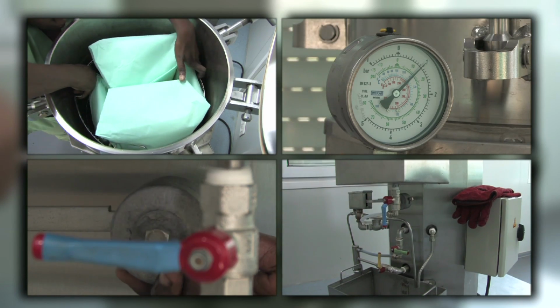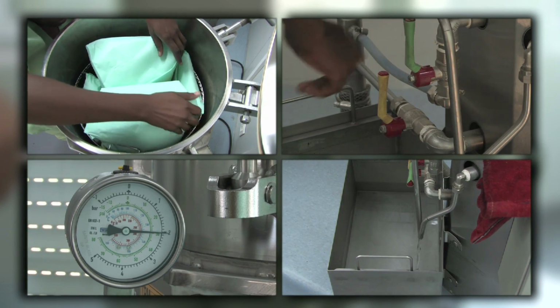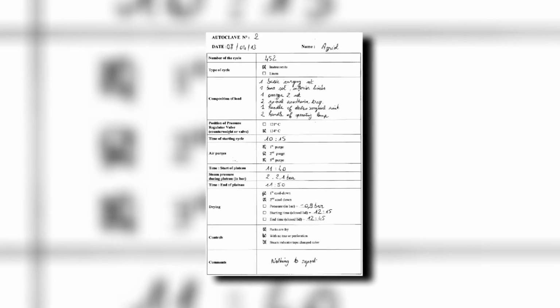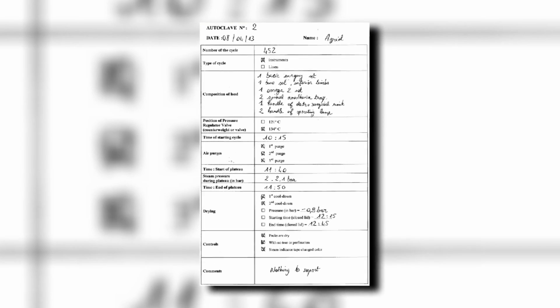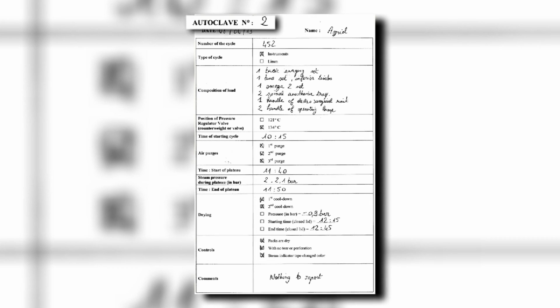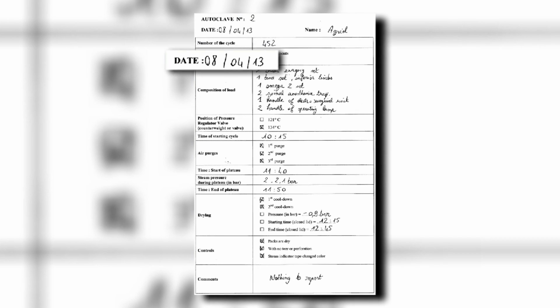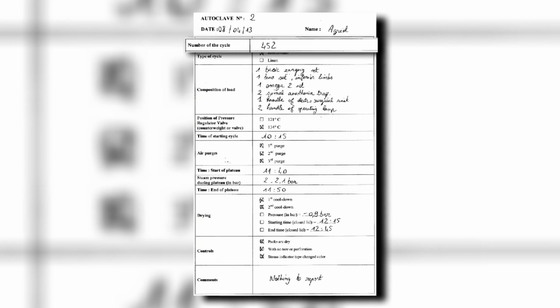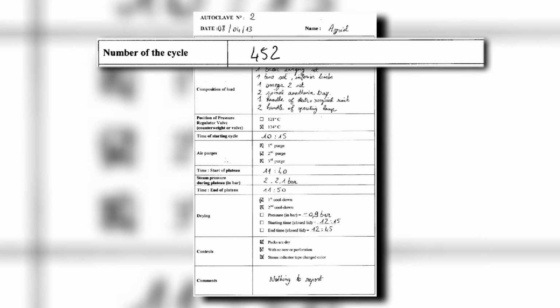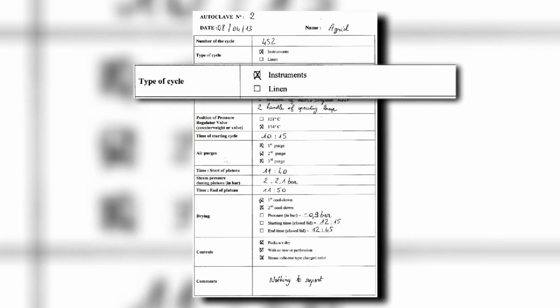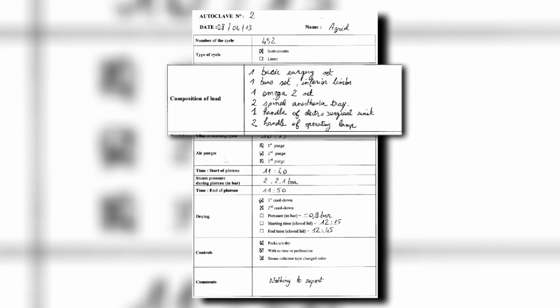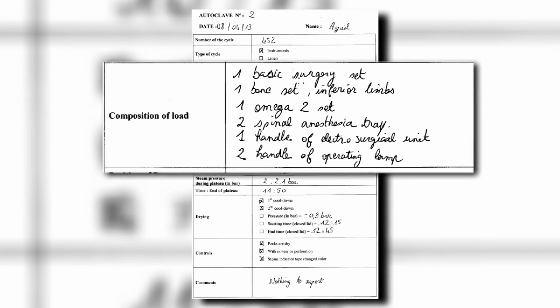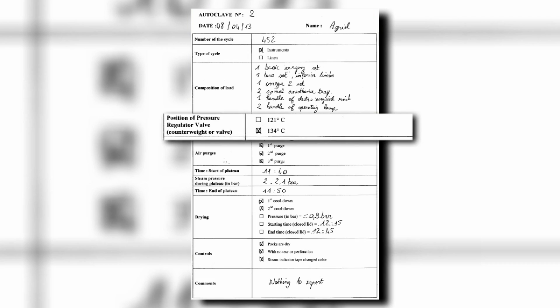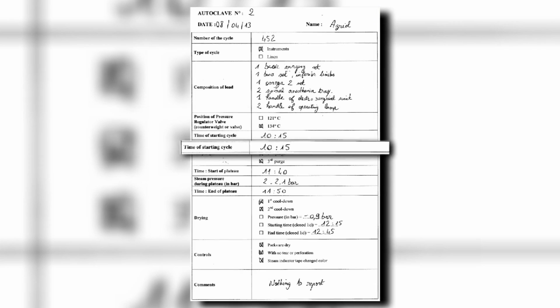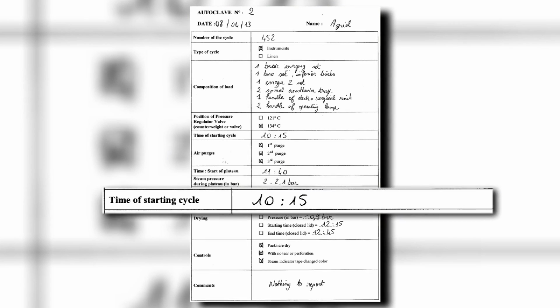Throughout the cycle, the person in charge of the cycle fills out a sheet, ensuring that every step is done. That sheet is also used for tracing the loads. Each sheet should have the autoclave number, the date and the person's name filled out, then the cycle number, the cycle type chosen, instruments or linens, the composition of the load, the pressure valve setting, the 134 degrees Celsius or 121 degrees Celsius cycle, the start time for the cycle.